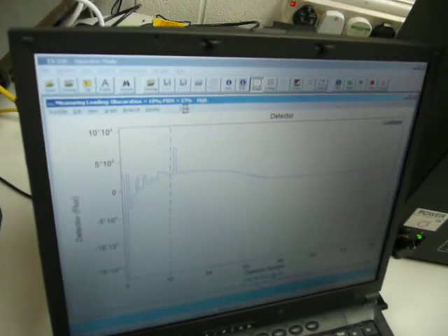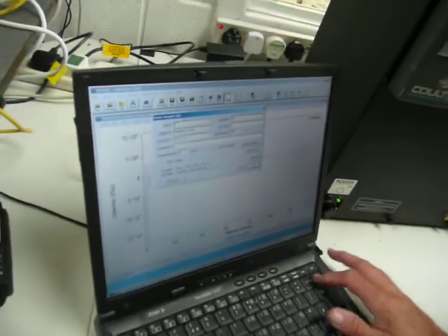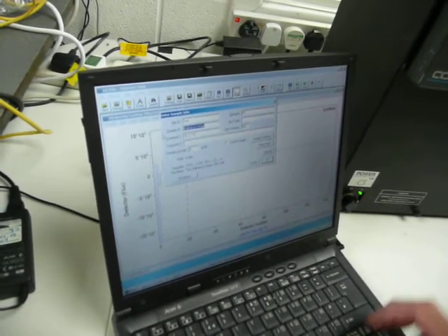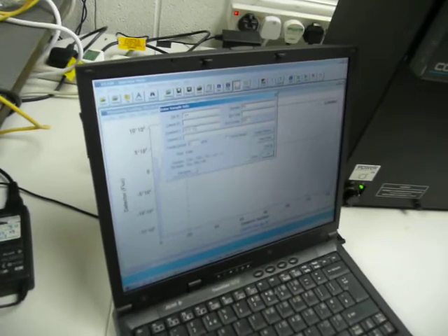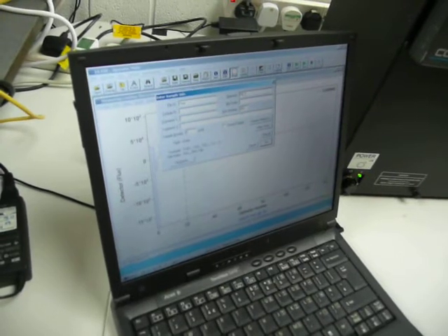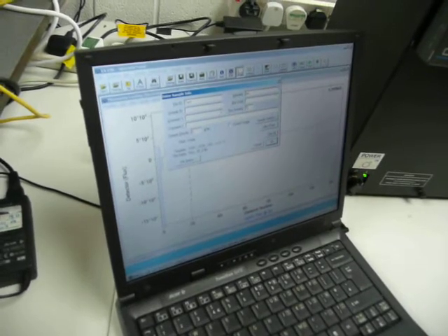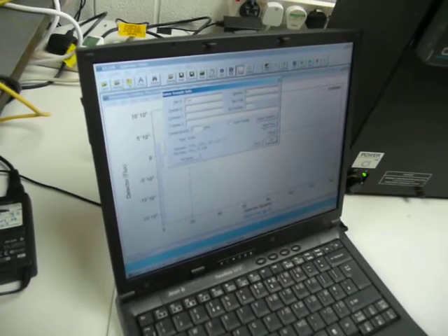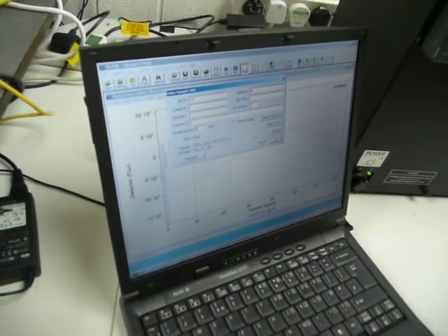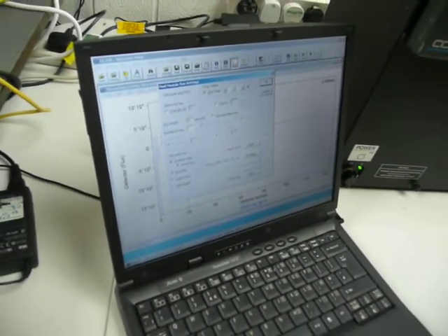Yeah. And it then gives you the opportunity of entering in the sample information. Okay. So whatever the sample is, I'm going to call this test. If there's any particular sample ID, we'll take that one out for the time being. I'm operating it, so put my initials in. Run number, I generally start the day at 1. Fluid you need to select, well, it's water in this particular case. Other than that, if you want any other comments, you can make them there. Otherwise, just click OK.